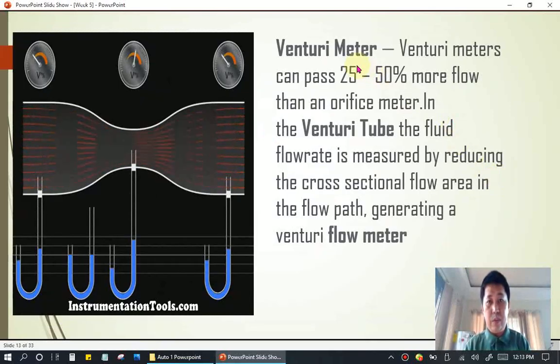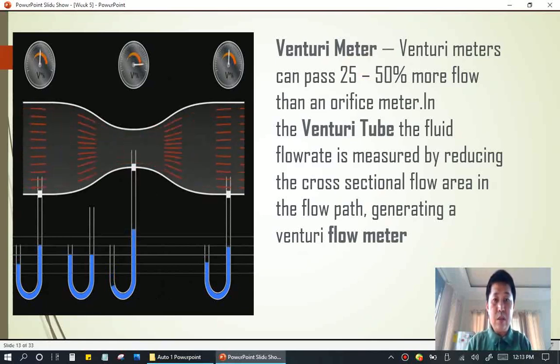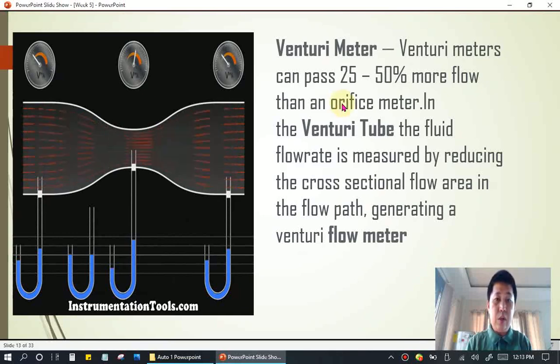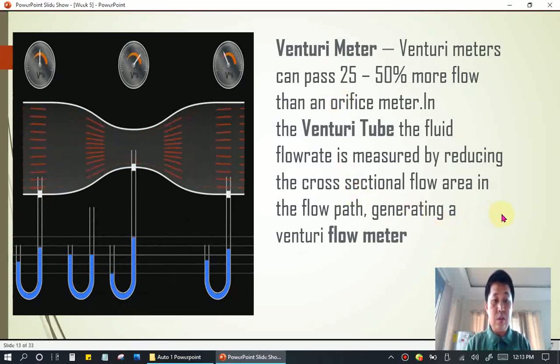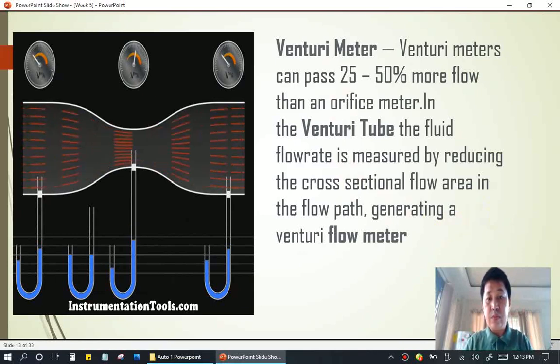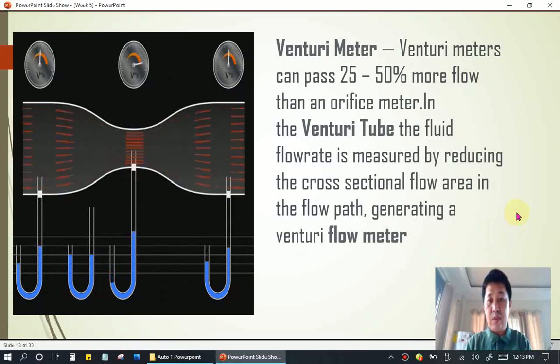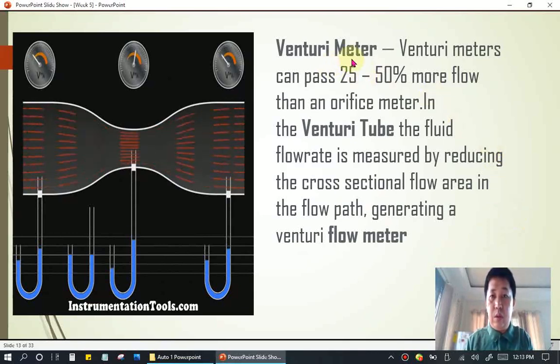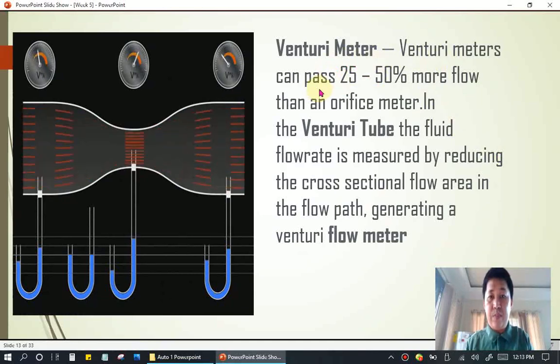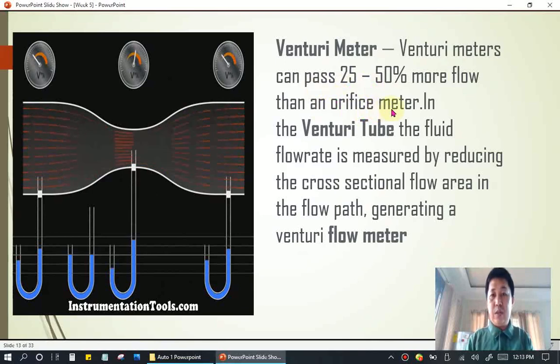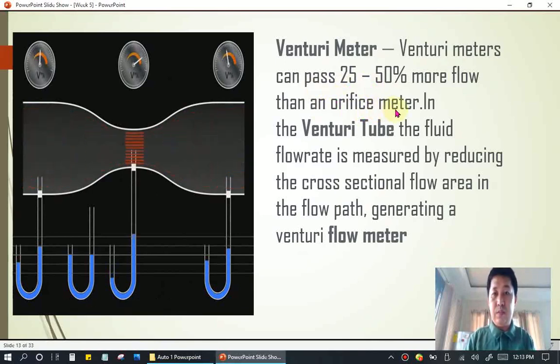Next, we have the venturi meter. So there are a lot of flow measuring devices, but I only show you just a few, because we only need to discuss a few examples. So venturi meters can pass 25 to 50% more flow than an orifice meter.